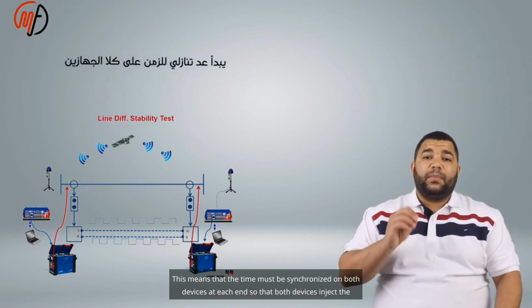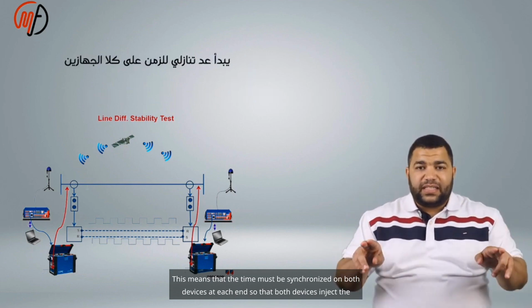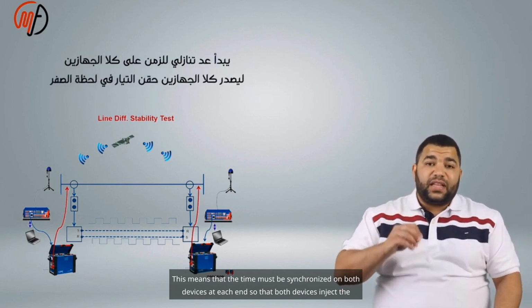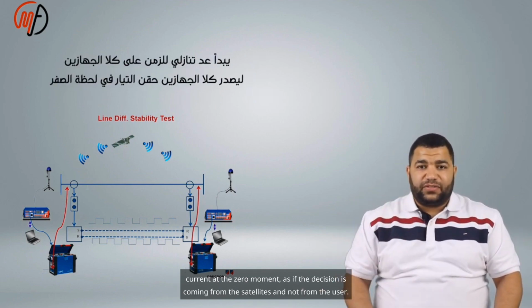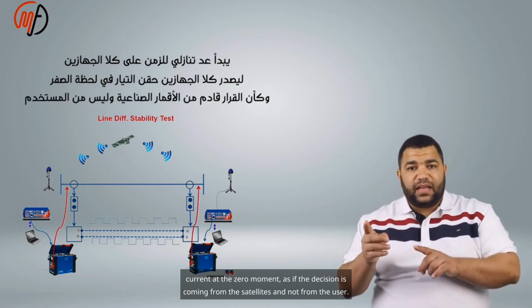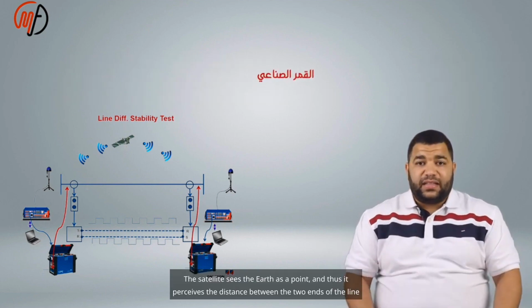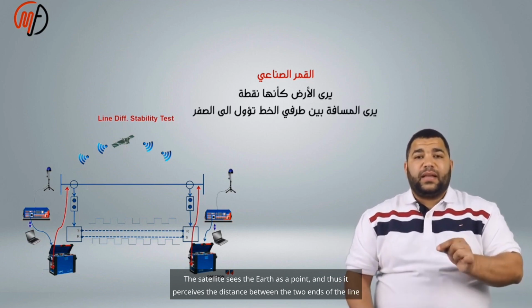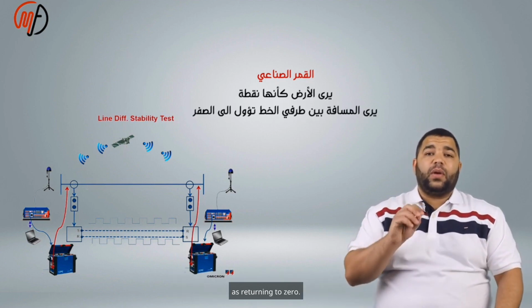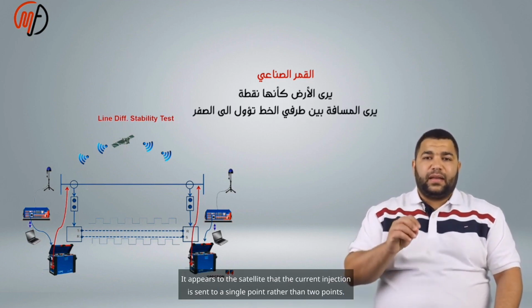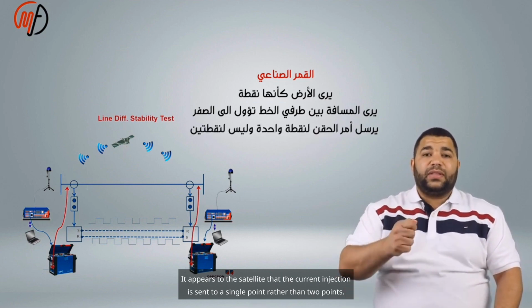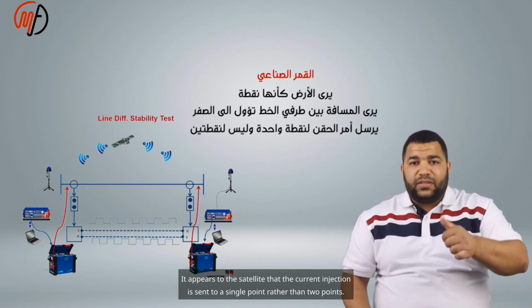This means that the time must be synchronized on both devices at each end, so that both devices inject the current at the 0 moment, as if the decision is coming from the satellites and not from the user. The satellite sees the Earth as a point, and thus it perceives the distance between the two ends of the line as returning to 0. It appears to the satellite that the current injection is sent to a single point rather than 2 points.